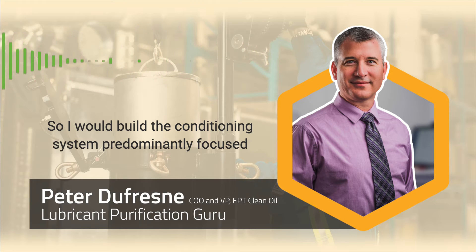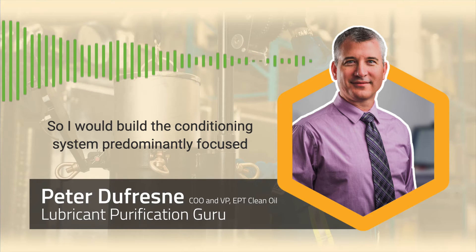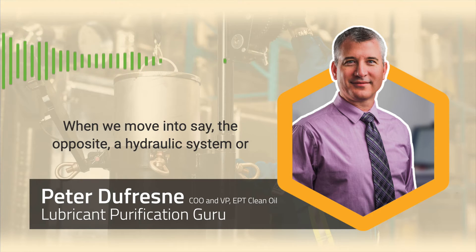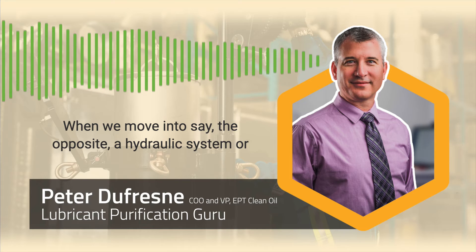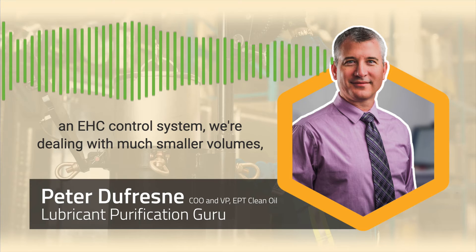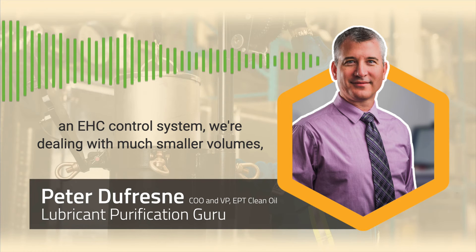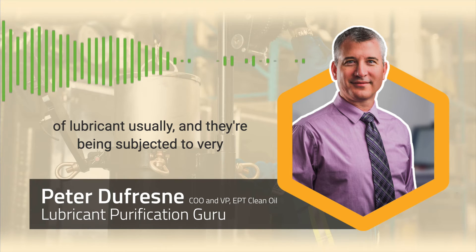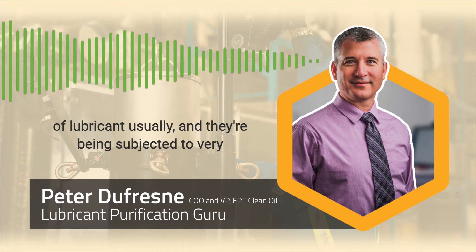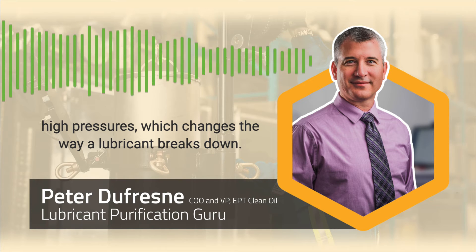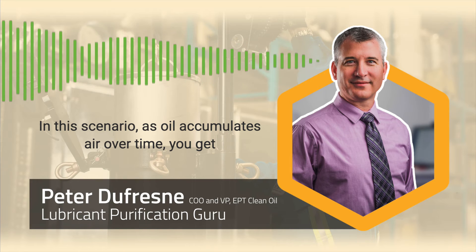So I would build the conditioning system predominantly focused on ICB ion exchange technology, followed by a particulate filter. Moving to the opposite scenario — a hydraulic system or an EHC control system — we're dealing with much smaller volumes of lubricant, and they're being subjected to very high pressures, which changes the way the lubricant breaks down.